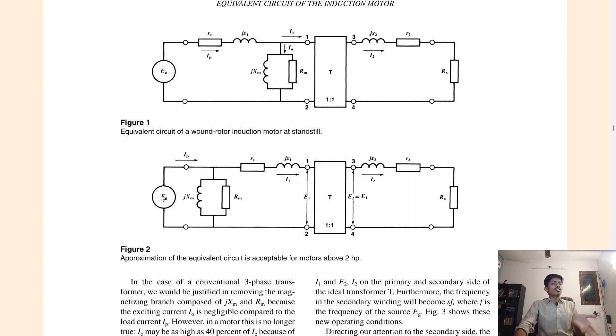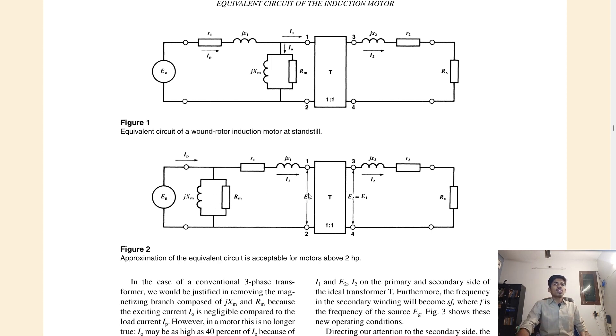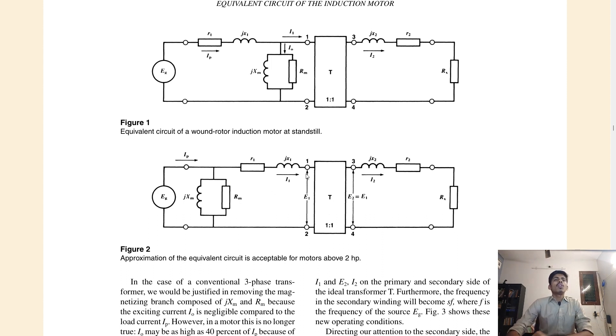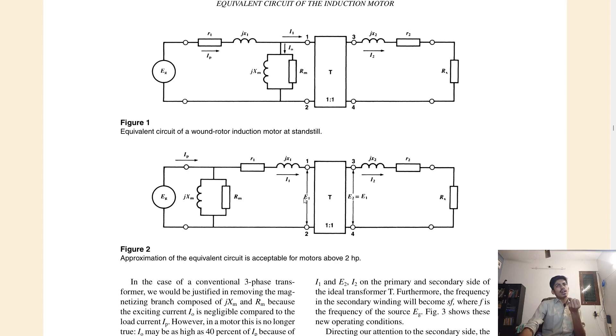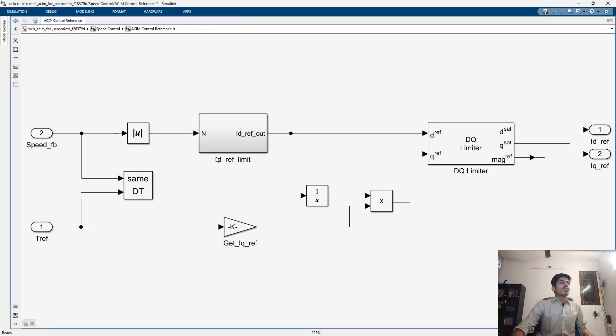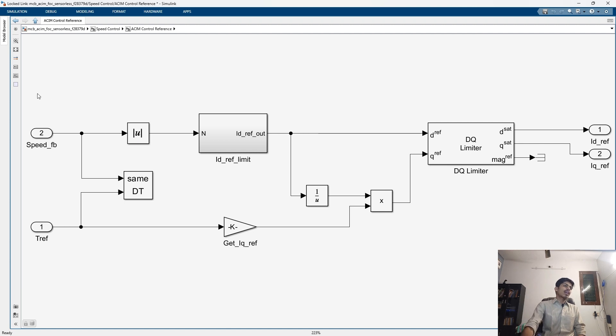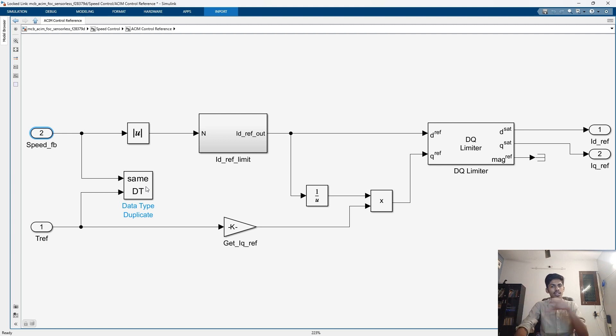If the back EMF is large — say 190V against a 200V terminal voltage — the difference is small and less current flows. The back EMF depends on flux and rotor speed: the faster the rotor spins, the higher the rate of flux change in the stator, the larger the back EMF, and the less current flows. To control speed we can indirectly reduce the flux. This is called field weakening — the direct axis current is also called the flux-producing current. In DC machines lab we have done field weakening: weakening the field allows the motor to run faster beyond rated speed.